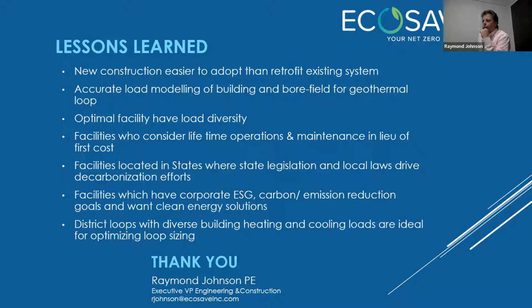We model buildings to determine heat loads and cooling loads, and from that we size boilers, cooling towers, and chillers. But here, that's not the case. We have something dynamic: heat transfer between the heat pump loop and the ground. So we have to model not only the building but also the bore field and how it performs, becoming an integrated model, because we don't really have a second chance. You size the building and the bore field, and if the bore field doesn't work, it has to be augmented, which we don't want to do. So it's imperative we have a proper model for both.